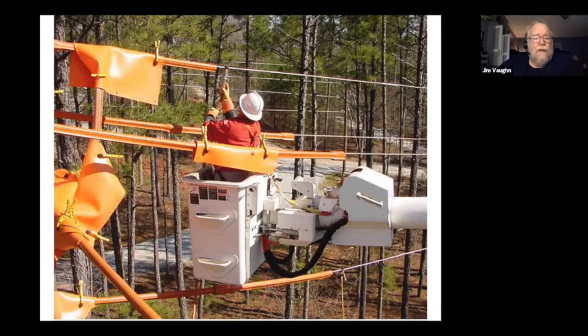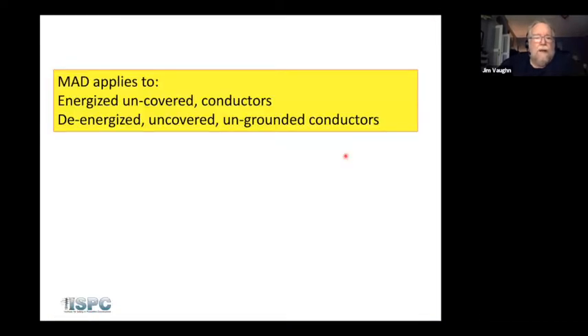And here's what I'll tell you that we find over years and years of work. Right here, we have the structure, or the pole is right here on the edge of this picture. And what you see here is 1, 2 rubber hose. Same thing here, 1, 2 rubber hose. On the side of the pole where you're working with the bucket, it is very hard to legally be properly covered without using 3 line hose sections on the side of the pole that you work. Now, if you recognize that this is the measuring point for MAD back up to the worker, then you'll understand why 3 hoses are necessary to make that work. So MAD applies to energized uncovered conductors and de-energized uncovered ungrounded conductors, depending on what the mode is that you're working in.